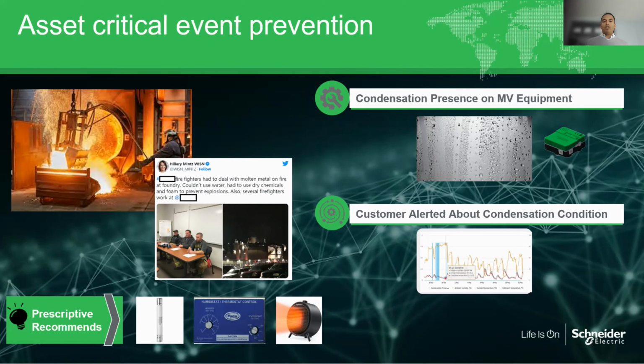This switch was shipped without a humidistat. Basically, that humidistat is a little sensor that ships with this type of equipment, supposed to turn on the heater when humidity levels start rising. We talked to the manufacturer of this particular switch — which I'm also not going to name — and we started digging into this. It turns out that for this particular part of the country, they don't ship the switches with a humidistat, because traditionally, historically, humidity has not been a problem here.